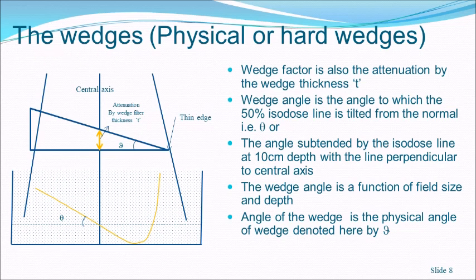Next, we discuss wedges — mainly the physical wedge, also called the hard wedge. Soft wedges are also available today under names like dynamic wedge, virtual wedge, and motorized wedge. Physical wedges are still used with cobalt units and even with linear accelerators. When a physical wedge is introduced in the path of the beam, there is attenuation of radiation — greater attenuation on the thicker side and less on the thinner side.